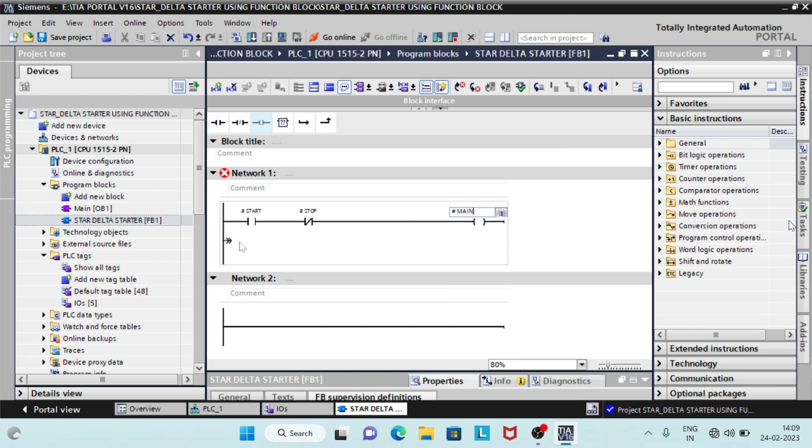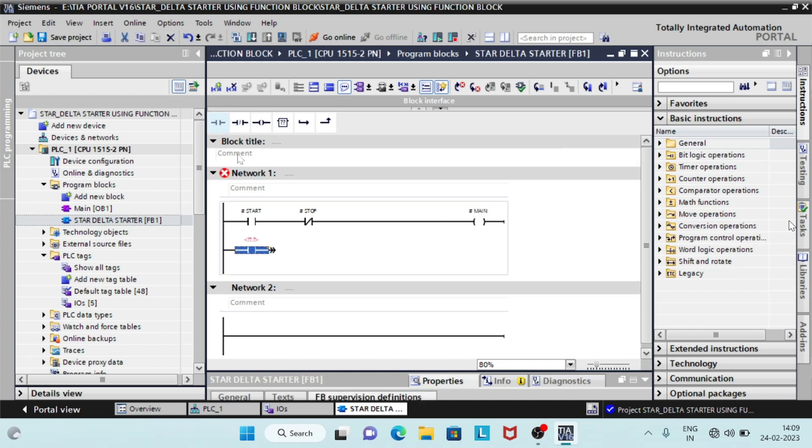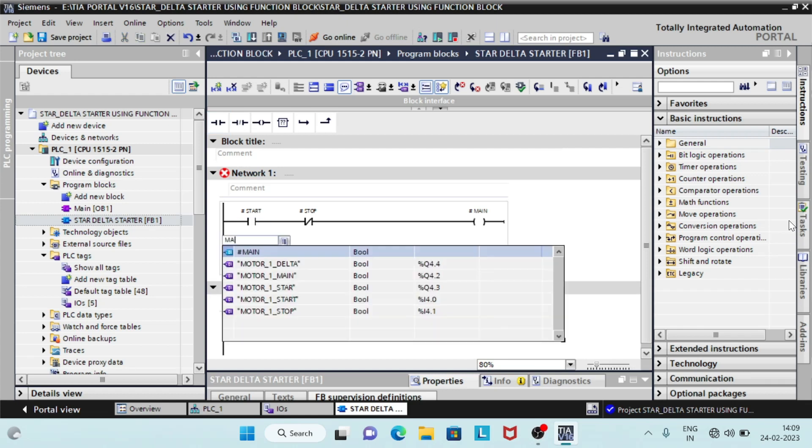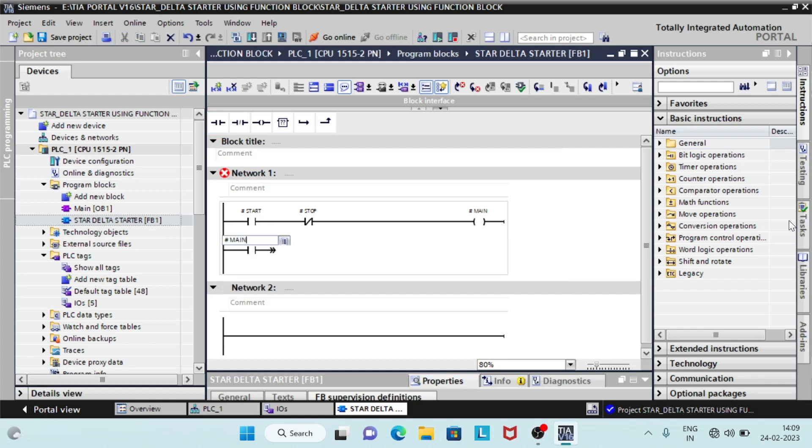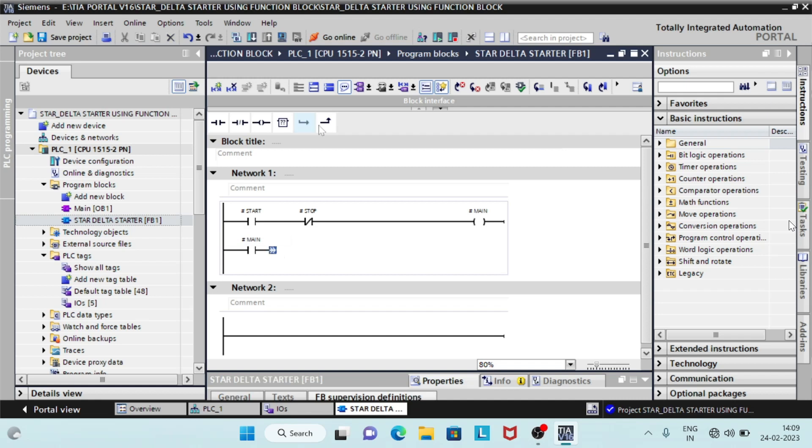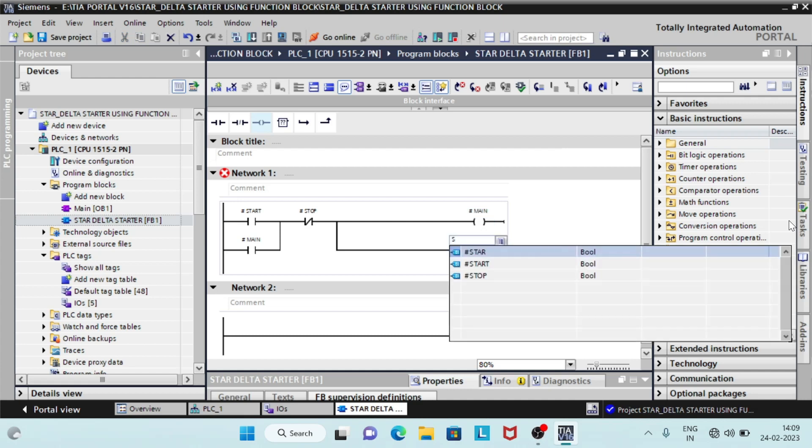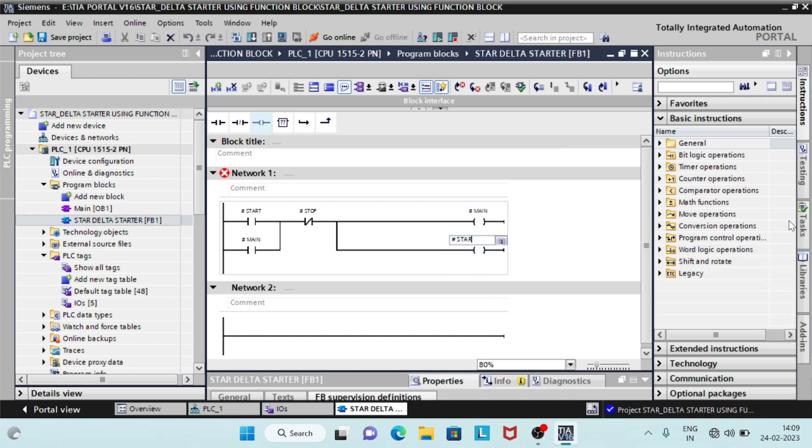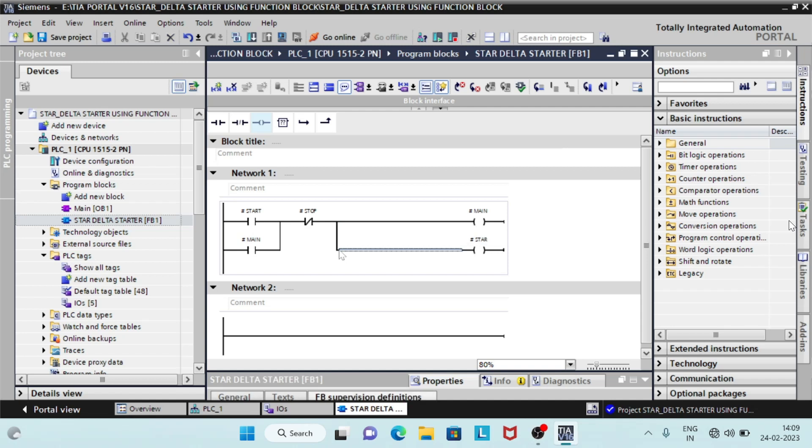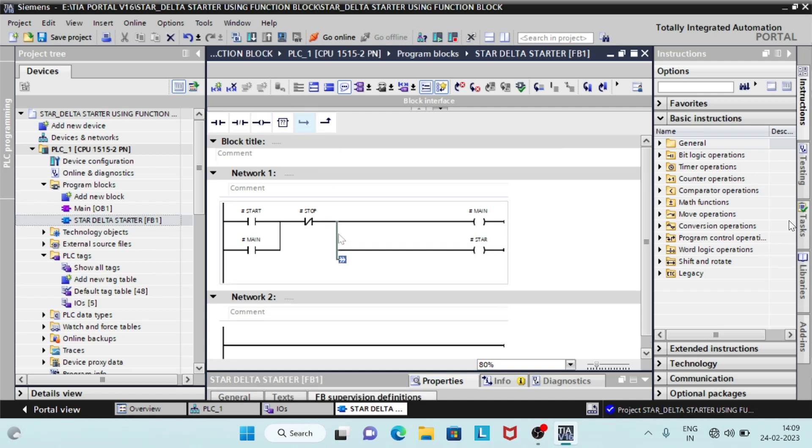We will latch our start circuit by using contacts main, so that it will remain on after the button is released. Make branches after the stop button for star and delta contacts. Enter in on delay timer, t on. It will energize the delta coil after preset time of 18 seconds.